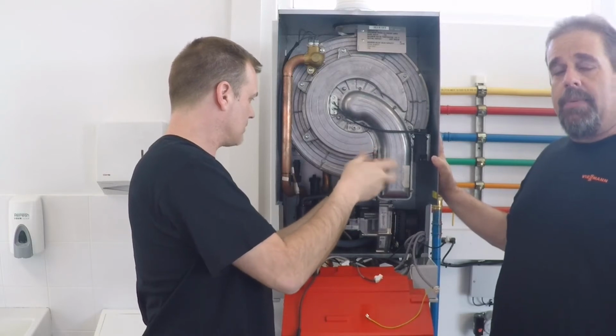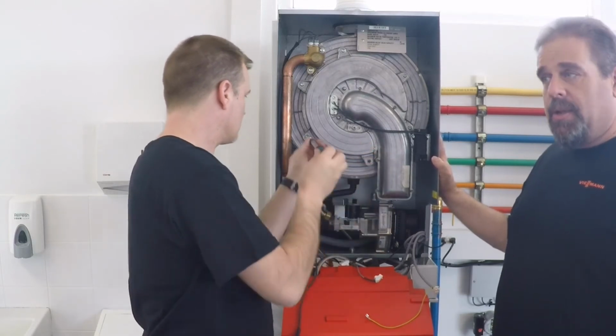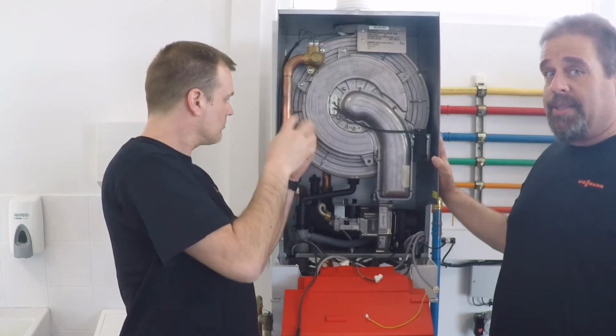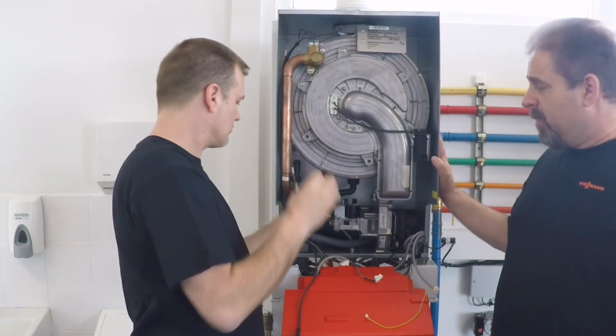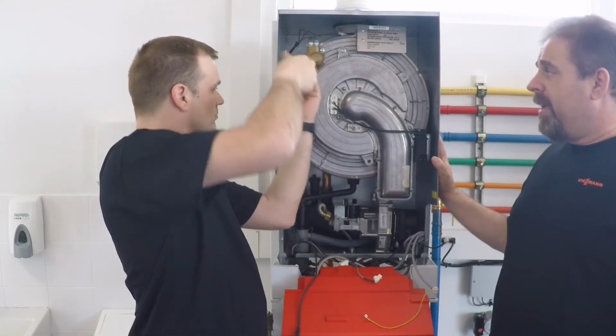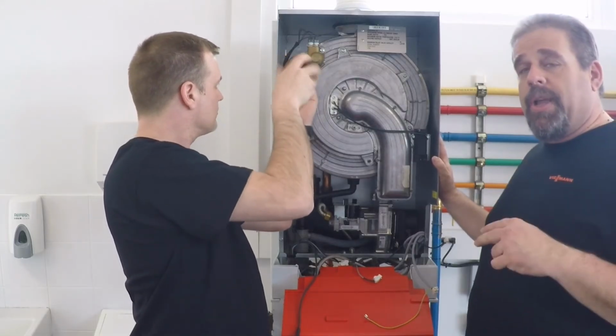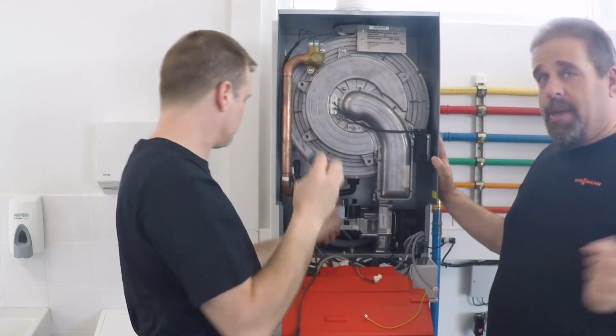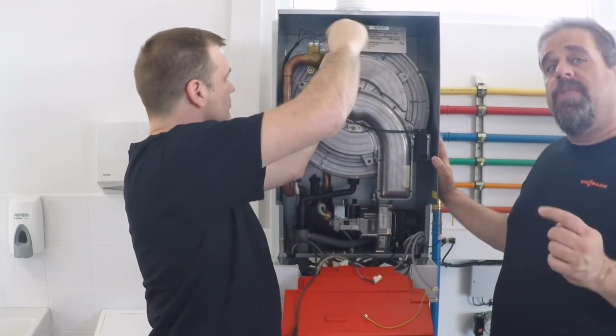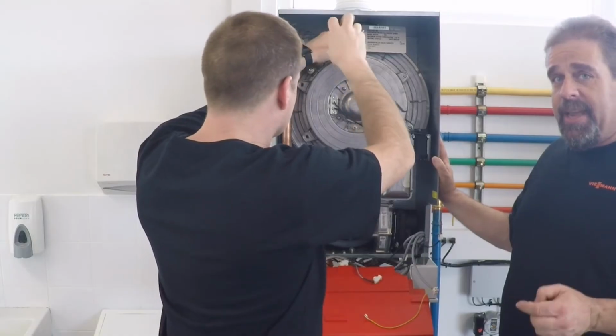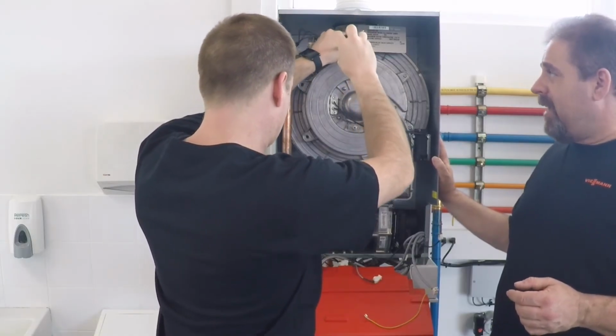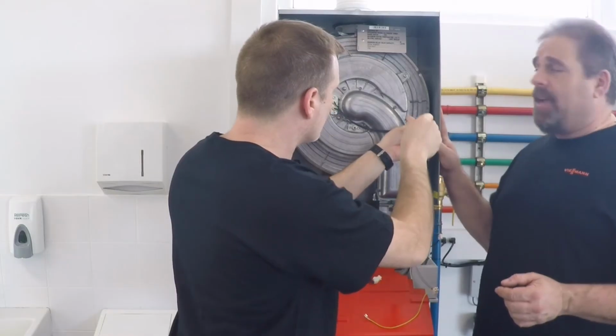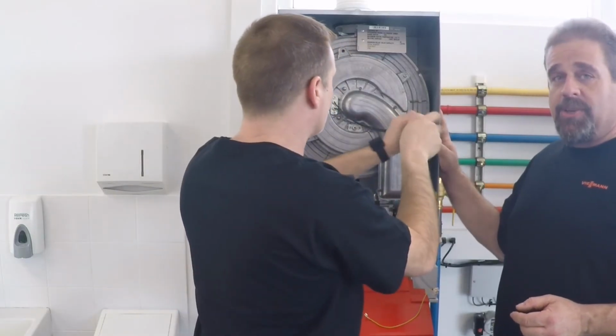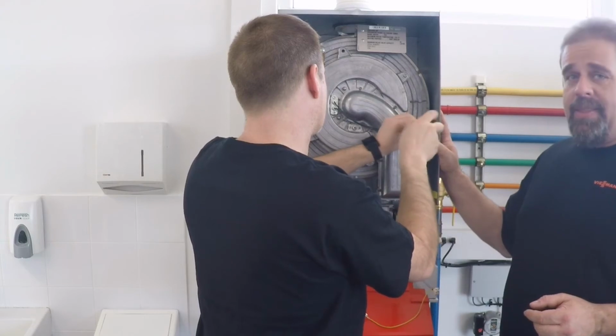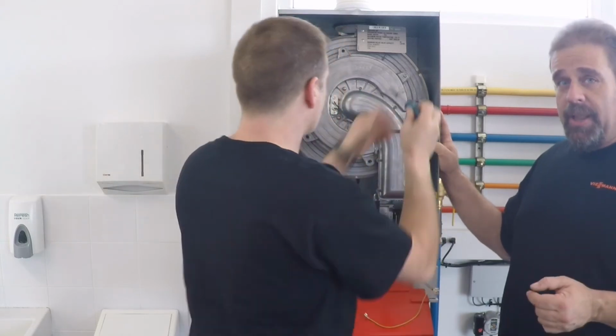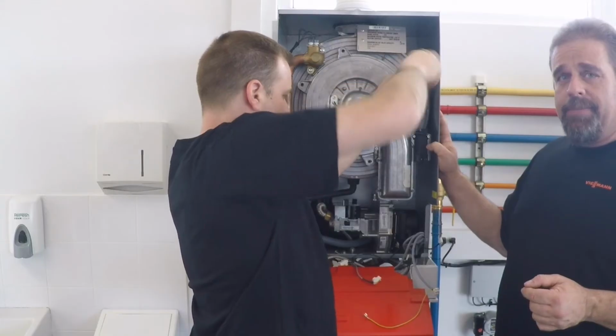This heat exchanger takes minutes to access. Unlike competitors, where it takes a lot of time to access a heat exchanger, with a Viessmann product it's very quick. The good thing is no matter what model Vitodens you're working on, a B2HA, a B2B, a B2A, the heat exchangers all remove the same way. They're all just as easy to get into. So we want to make it easy so the contractor can actually access and clean, if needed, the heat exchanger every year, and gap and clean the ionization electrode and the ignition electrodes, and check the burner gasket as well.